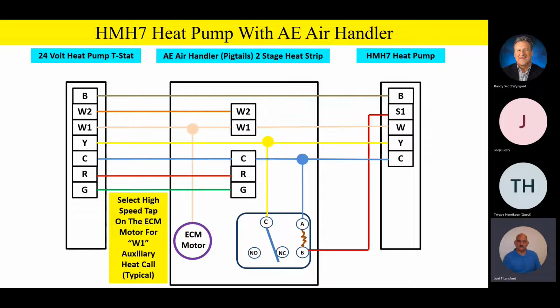You'll also notice on the ECM motor, remember we took that yellow wire off. We're going to select a high-speed tap on the ECM motor, and we're going to hook it up to W1. So here's the idea: if I have an auxiliary heat call, or during defrost, if I get a W call from the outdoor unit, anytime we have a W1 auxiliary heat call, it's going to energize the high-speed tap on the ECM motor and call for high-speed operation.